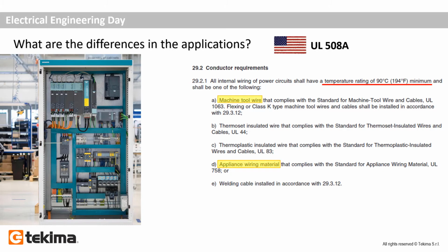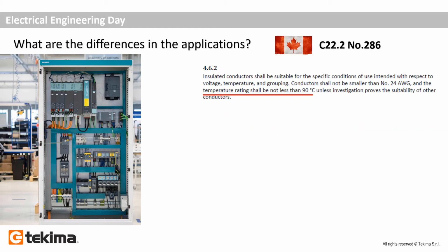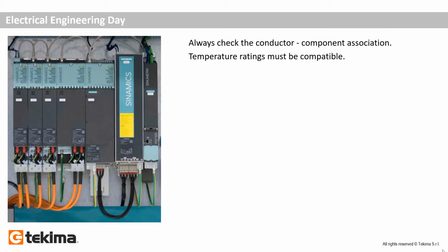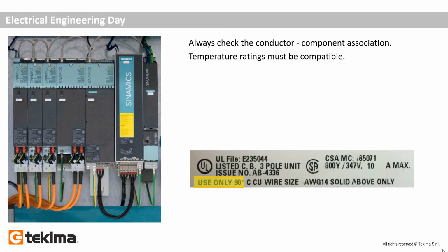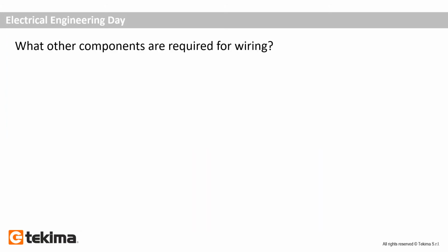Machine tool wire that is listed cable, or AWM cable that is recognized cable, for internal wiring. Same thing for Canada, where the 90 Celsius rating is mandatory too. One important thing is to double check the temperature rating of the cable and the temperature rating of the associated component. What other components are required for wiring?